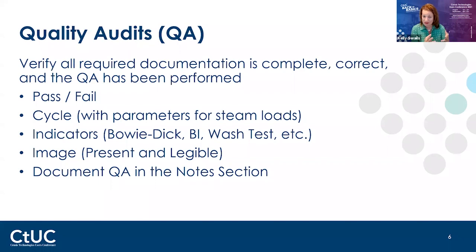And with that, if they have their error loads, run a monthly, quarterly, or annual report of your fails. You may find that sterilizer 3 has failed 3 times in the last month, but they ran it a second time and it worked. So no one told you about it. Well, maybe you have your sterilizer company come out and look at your sterilizer and say, why is this failing? Or you may find that it's error loads, it's all the same person.